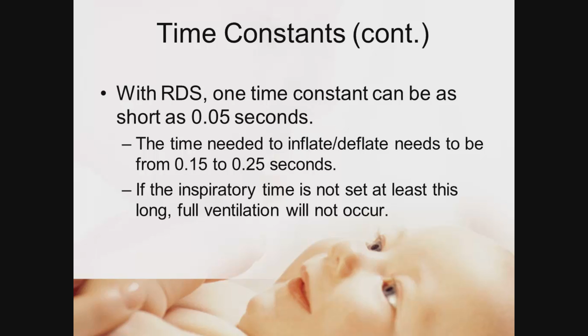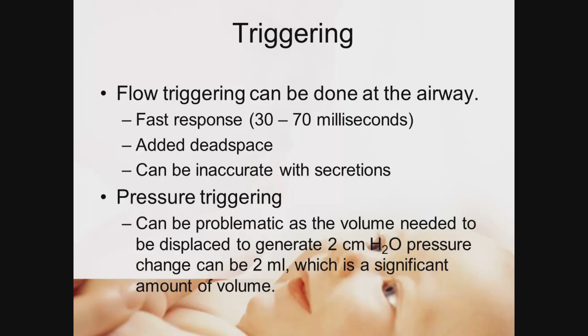Triggering becomes a real issue with these, especially with the micro preemies. They need a very fast response time, and especially if you have a flow sensor being utilized, if that gets contaminated with secretions, it can lead to problems with triggering. Pressure triggering is difficult because they have a very compliant chest wall, and a lot of the negative intrathoracic pressure that's created is transmitted across that wall, and the pressure trigger sensor never picks up on it. So we've looked at other options. How about if we put a sensor on the abdomen to notice when the abdomen is moving and use that as a trigger mechanism?